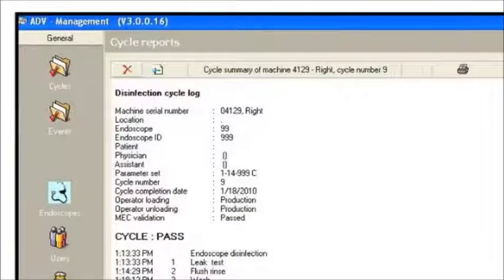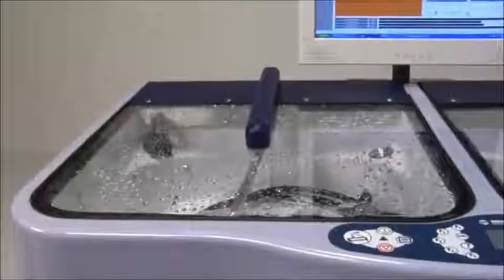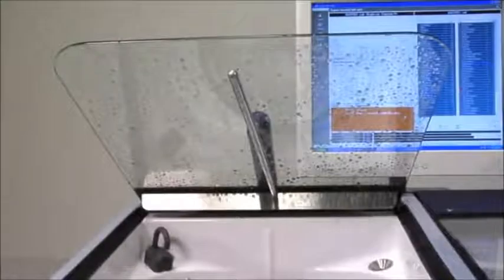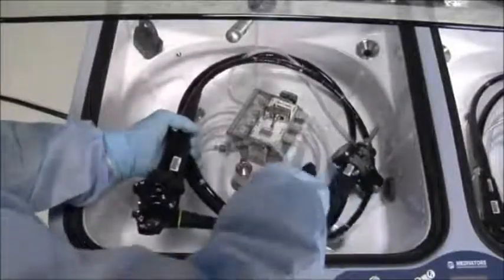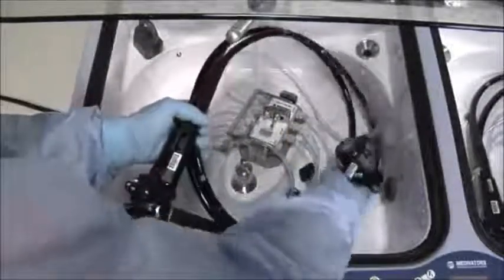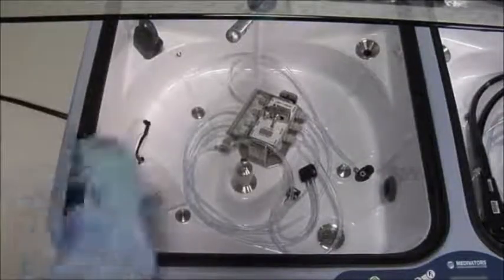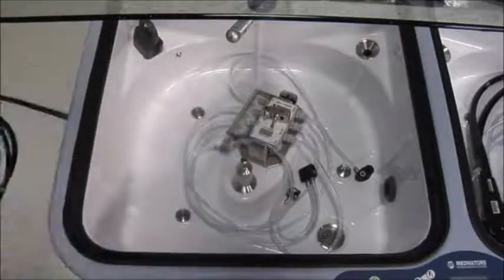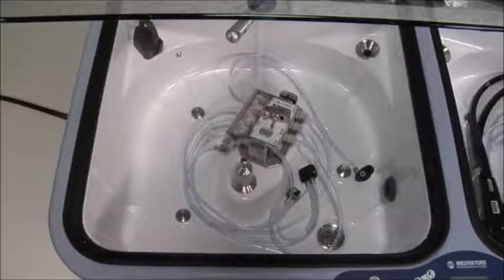The Advantage Plus will automatically store a record of the cycle, including all the ID data, cycle complete message with test strip pass or fail, and any error messages. Press the Open-Close button or foot switch to raise the basin lid and scan your operator ID barcode. Disconnect all connectors from the endoscope. Remove the endoscope from the basin and thoroughly dry all surfaces with a clean, lint-free cloth. Remove the accessory bag and dry and store the parts.